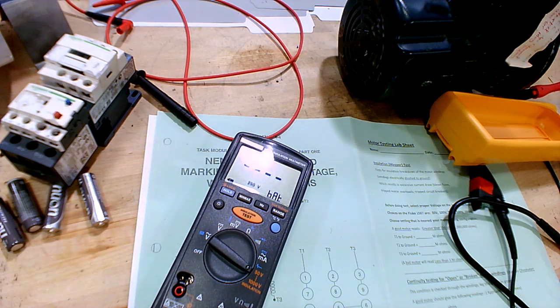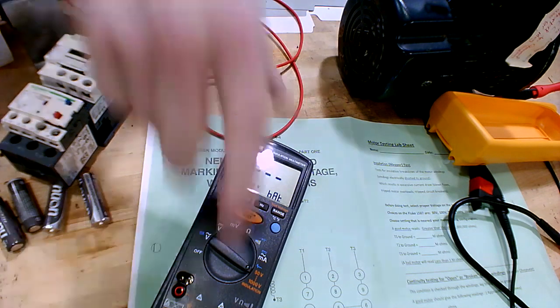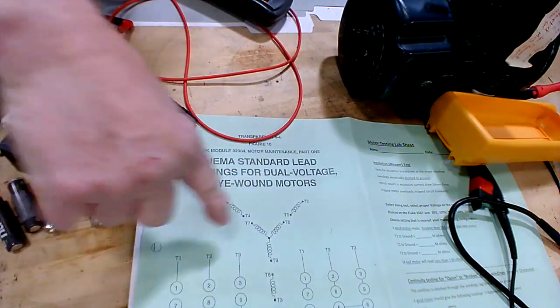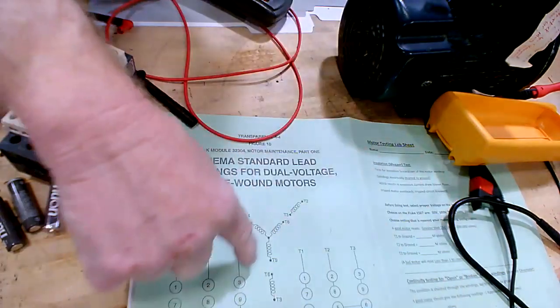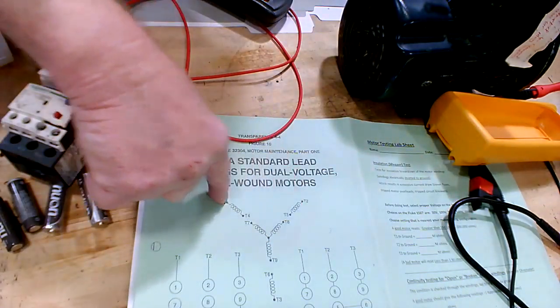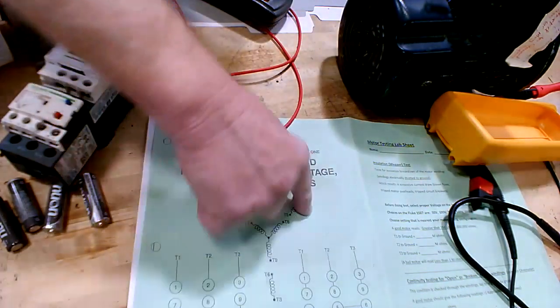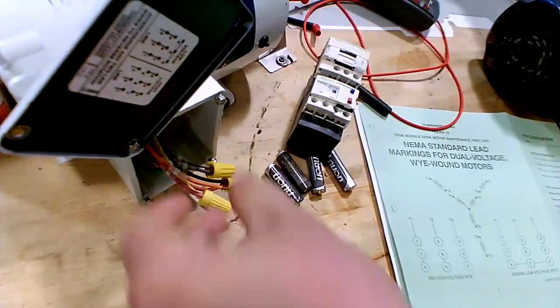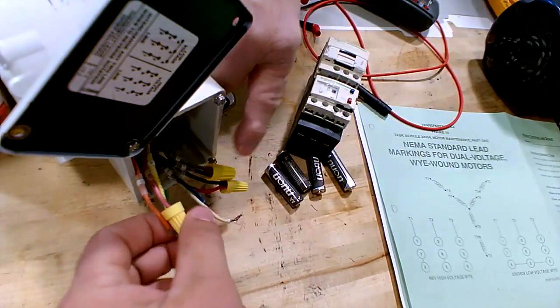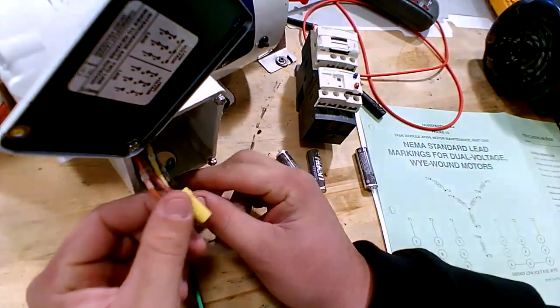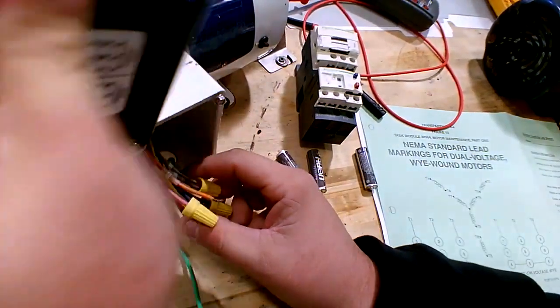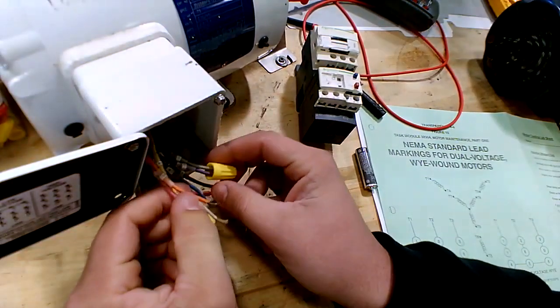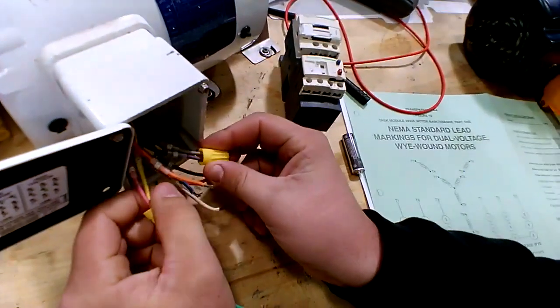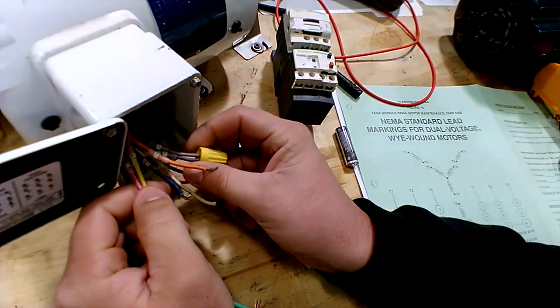Go ahead and make sure this is wired for high voltage, okay? Wired for high voltage, and then check through the windings like it says on step 2. Get a resistance reading from 1 to 2, 1 to 3, and 2 to 3, reading through it in ohms, regular ohms is the best. Okay? Make sure it's on high voltage. And be careful there about the camera.